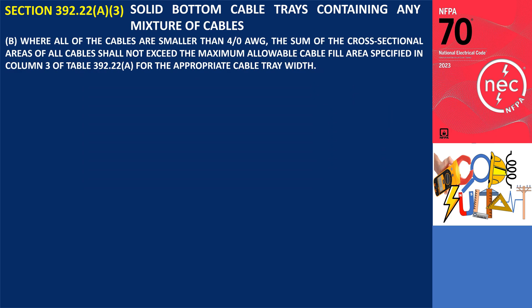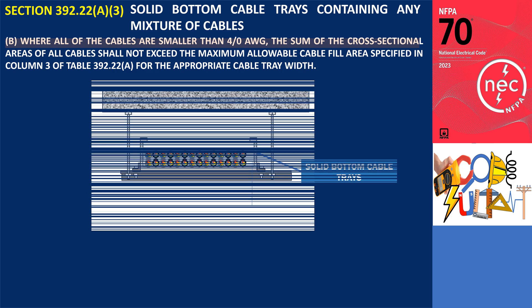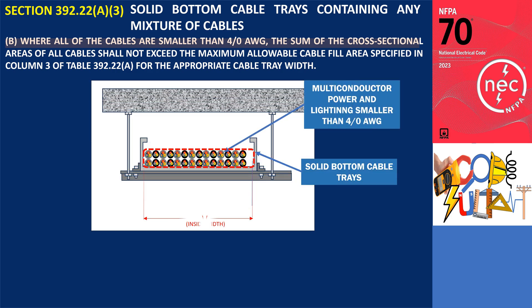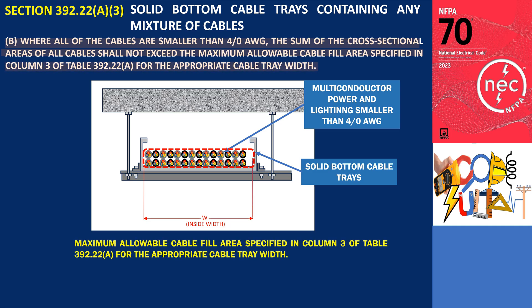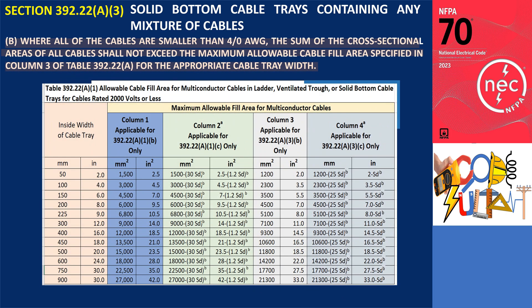Section 392.22(A)(3)(b) applies where all of the cables are smaller than 4-aught AWG. The sum of the cross-sectional areas of all cables shall not exceed the maximum allowable cable fill area specified in Column 3 of Table 392.22(A) for the appropriate cable tray width. This table provides the maximum allowable cable fill area for multi-conductor cables rated 2,000 volts or less installed in ladder, ventilated trough, or solid-bottom cable trays — which I have already discussed in my previous video.